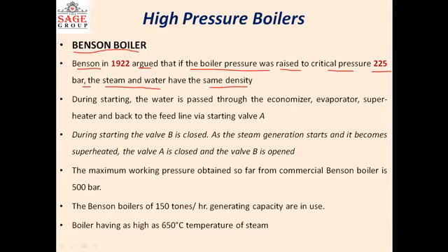So this principle was used in this Benson boiler, and at this pressure it will eliminate the formation of the bubbles. So definitely it will increase the steam generating capacity of the boiler as well as the efficiency of the boiler. So during starting, the water is passed through the economizer, evaporator, superheater, and back to the feed line via starting valve A. Next we will see in the figure the valve A as well as valve B.